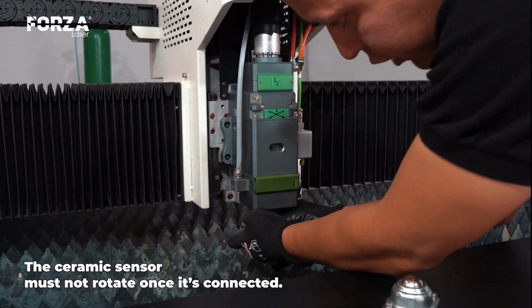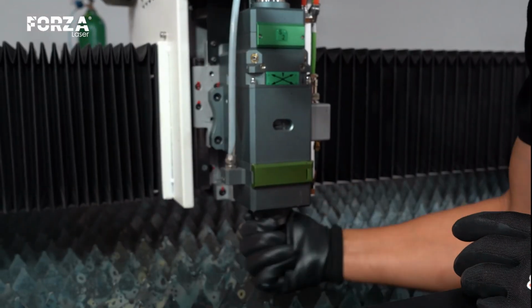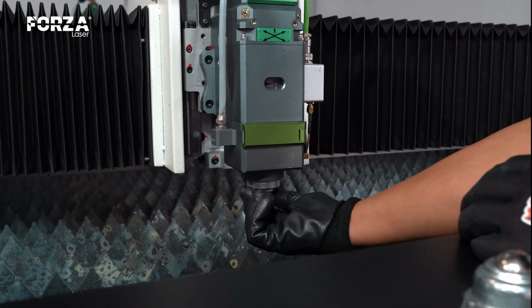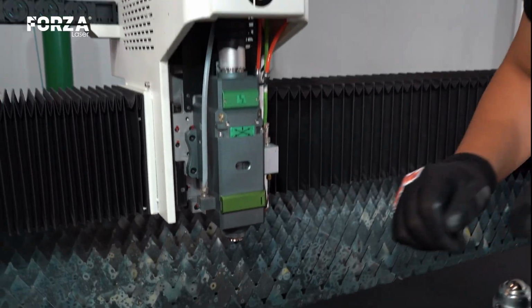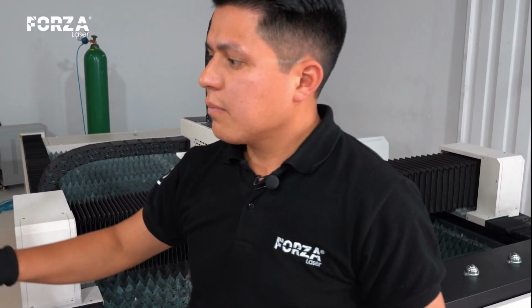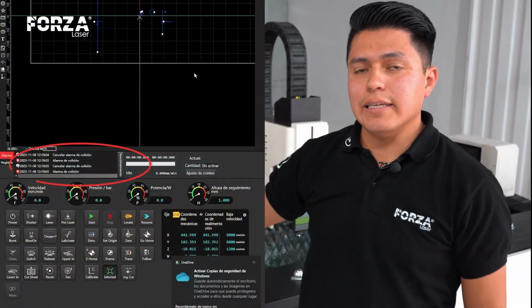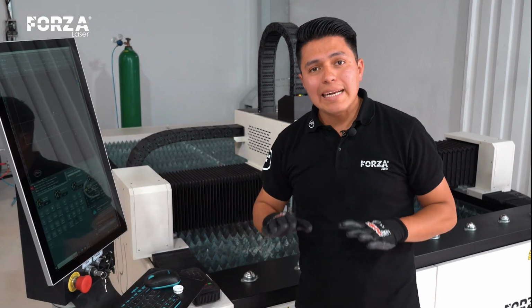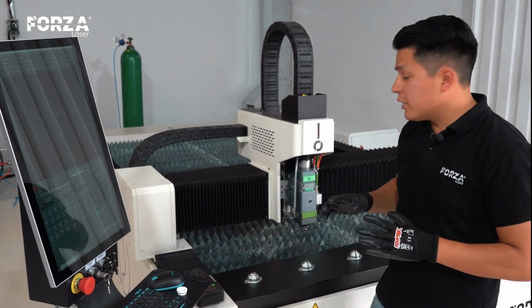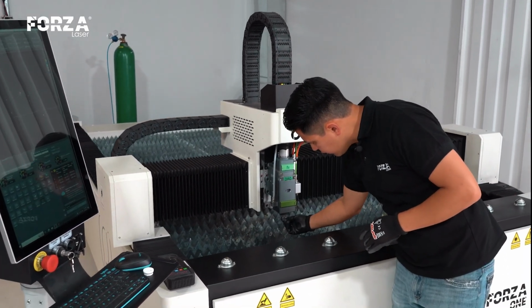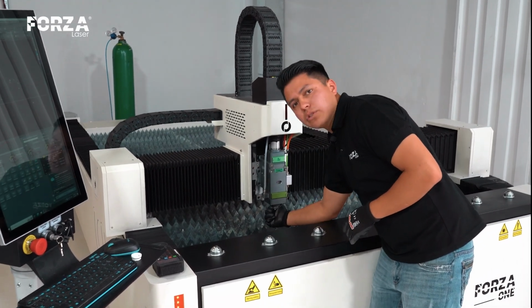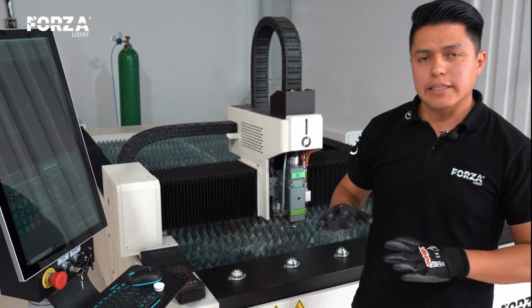We tighten it well and place the nozzle. Okay. We'll go closer to the screen, and we see the alarm has disappeared. To prevent this alarm, as a recommendation, when you change the nozzle and tighten it, additionally, you should also tighten the sensor's securing nut.